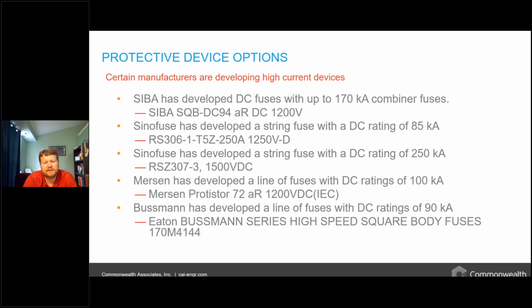I wanted to mention that although I don't have any connection to these manufacturers, we've done a lot of research and, through our experience, found a number of protective device manufacturers that have built equipment particularly designed to deal with these high DC fault currents and the upcoming battery energy storage market. With SIBA, we have some combiner fuses, which are very near the inverter and can handle fault currents upwards of 170,000 amps.